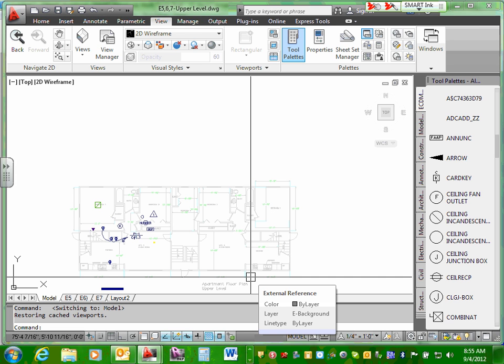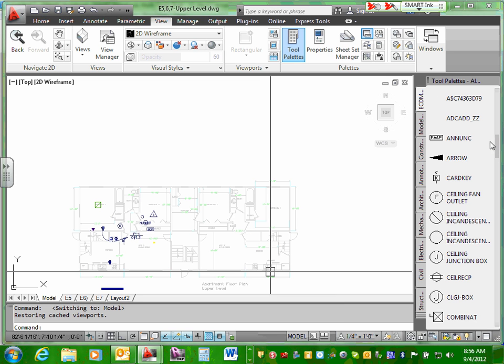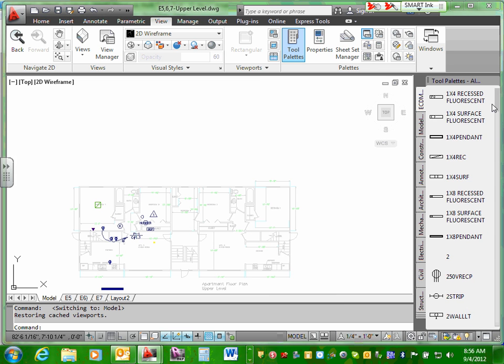We have a couple of options here. If you look at the symbols that we have — remember, the cheapest way of doing a dwelling is basically a surface-mounted fixture in the center of the room. The cheapest way is to have a surface-mounted fixture in the middle of every habitable room and hallway, switched by a switch. If you have a fan, you're going to have a fan-light combo typically in the bedrooms. Everything else, you can have a surface-mounted fixture in the middle of the room.